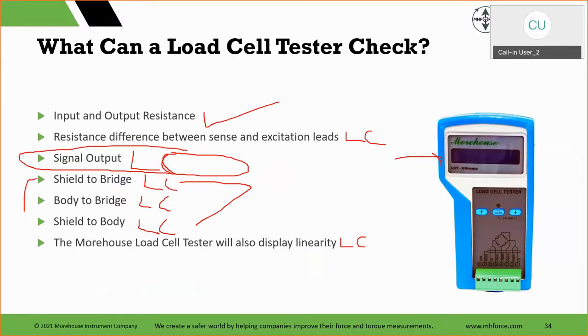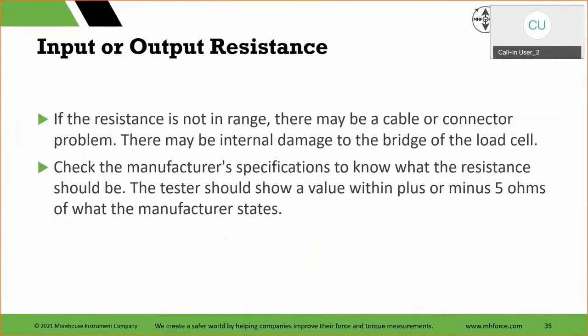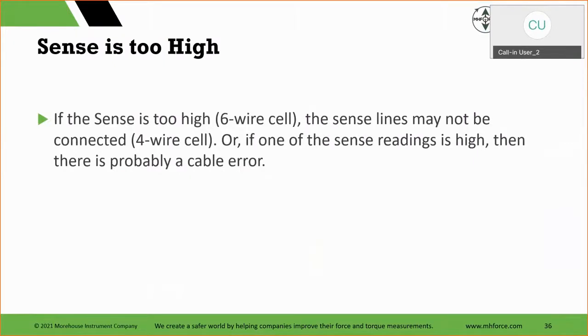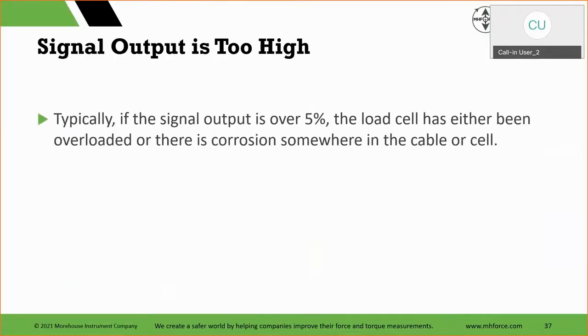That can tell you if you have some problems. Specifically, if you have grounding issues, this can tell you. A mega ohm meter costs over $1,000 to diagnose that, which the tester will. So some other things, if the resistance is not in range, there may be a cable or connector problem. There may be internal damage to the bridge of a load cell. Check the manufacturer's specification. Testers show the values within plus or minus 5 ohms. If the sense is too high, on a 6-wire cell, the sense lines may not be connected. That one people miss quite a bit. If they're wiring cables, they forget to wire sense. Or if one of the sense readings is high, then there's probably a cable error. And typically, if signal output is over 5%, the load cell has either been overloaded or there is corrosion somewhere in the cable, which the tester can check for.